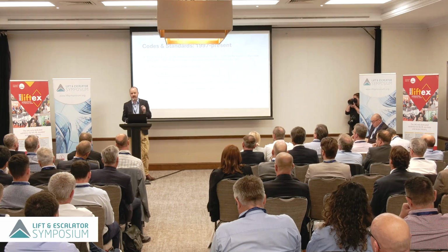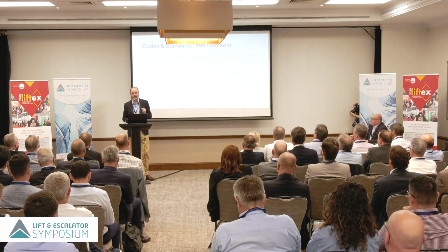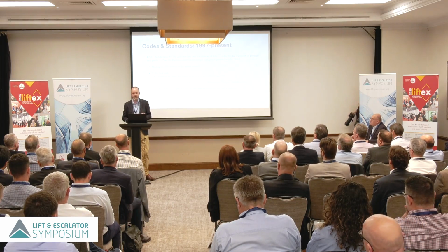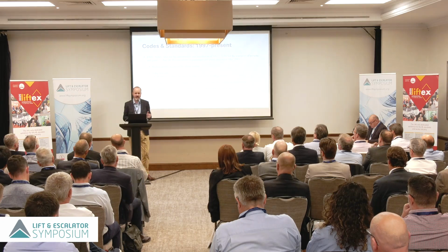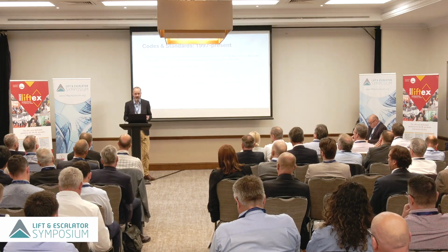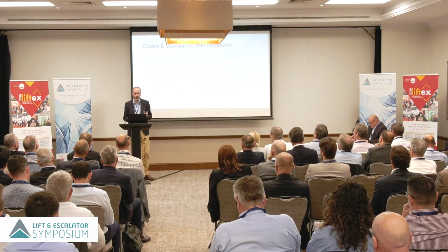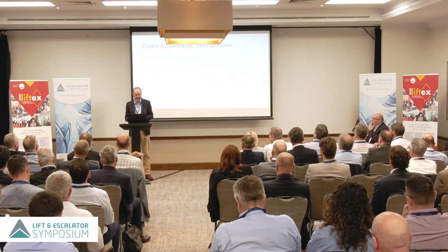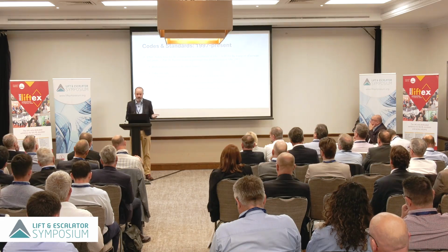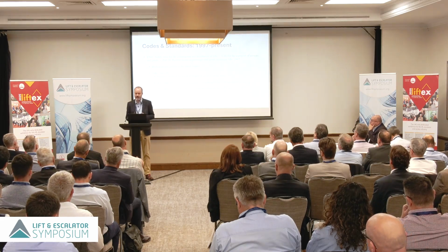It is a particularly macabre reason, but the reason is a human being can survive for 3 days without drinkable water. So when we talk about the call being every 3 days, it is based on the assumption that somebody is stuck in there for the full 3 days without water. A particularly unpleasant thing to think about. Most designs use that same DTMF signaling to place and register their test calls.